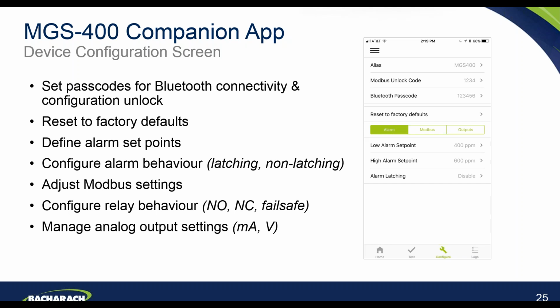On this screen as well, useful for configuring your alarm behavior. So you can set your alarms to be latching or non-latching. You can adjust your Modbus settings on here. And you can configure your relay behavior. So you can have your relay set to normally open, normally closed, or fail safe. And you can also manage your analog output settings here. So you can set that to be milliamps or volts. Again, really to provide that flexibility to meet the specific project and the requirements that you have per installation.